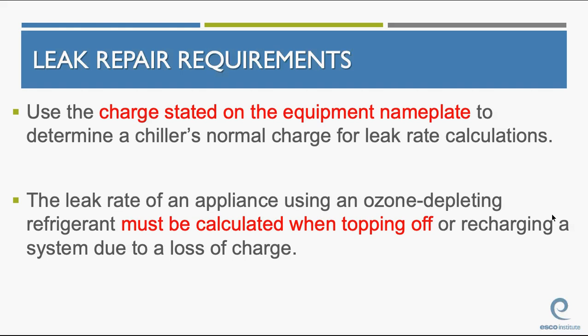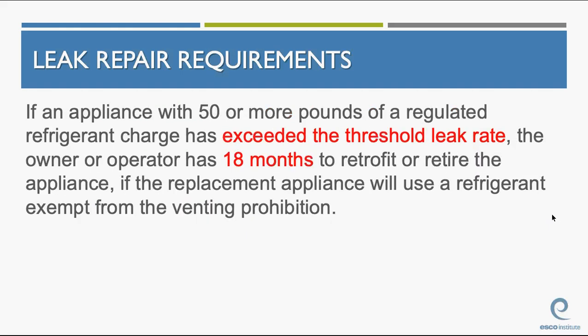Again, we use the charge that's stated on the equipment nameplate for chillers. It's usually very easy because it is a complete package with all the refrigerant right there. The leak rate of an appliance using an ozone-depleting refrigerant must be calculated when topping off or recharging a system due to a loss of charge. Again, we do have to look at it. We do have to say, am I charging more than the acceptable leak rate? Because if we charge more, we have to put a plan in action.